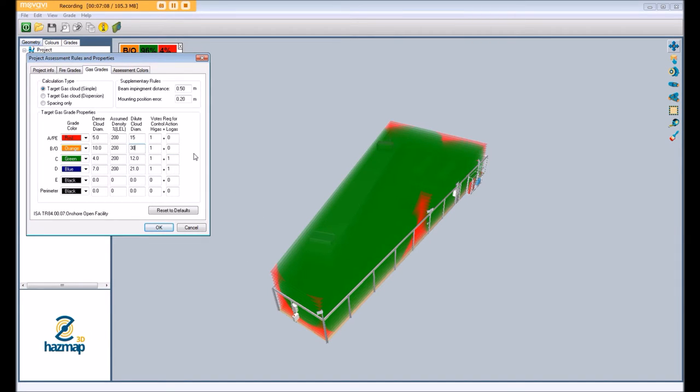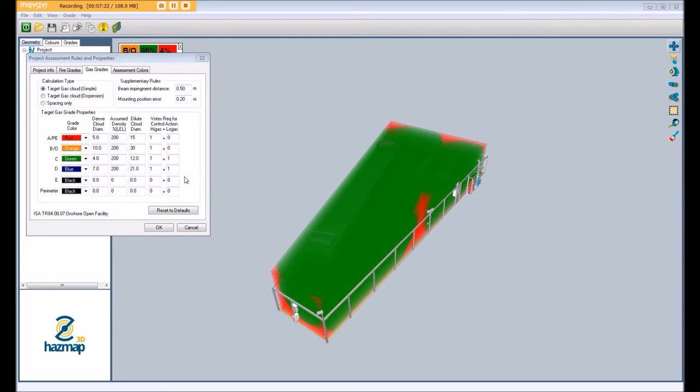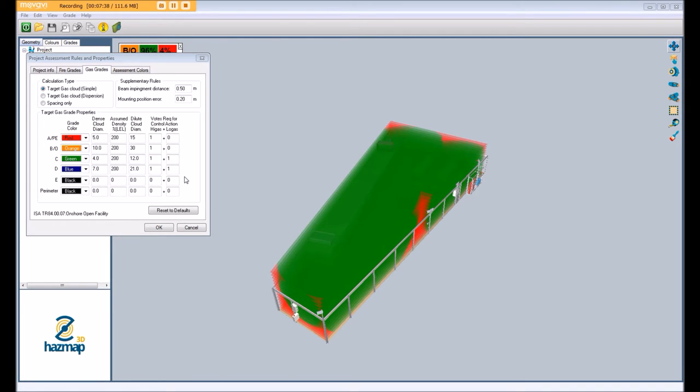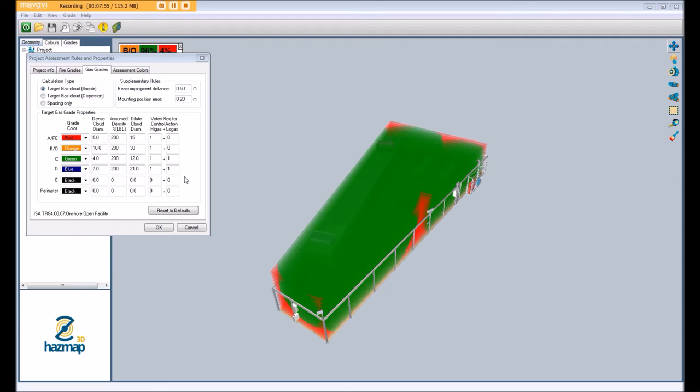Now this information actually comes from literature reviews over the last 15 years on gas cloud behaviour in semi-open based congested areas. Obviously the main driver behind the performance of the gas detection system is going to be the congestion and the confinement in the given area as that is the main driver behind how volatile an ignition of that gas cloud can be. This is often referred to as the simple 5 meter spacing or the target gas cloud methodology. But Micropack take it a little bit further, introduce a little bit more engineering judgment and include the target gas cloud which includes dense and dilute clouds. Essentially we are completely aware that the gas cloud will disperse and will accumulate within the area. But using the target gas cloud method we don't try and predict exactly where that gas will go. Obviously that method is applicable and Micropack can carry out that analysis. But with the target gas cloud essentially we are incorporating well established principles of gas dispersion based on empirical evidence to allow performance based design using specified target gas clouds.